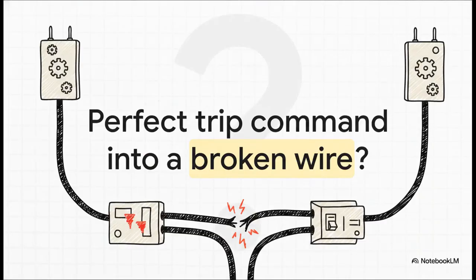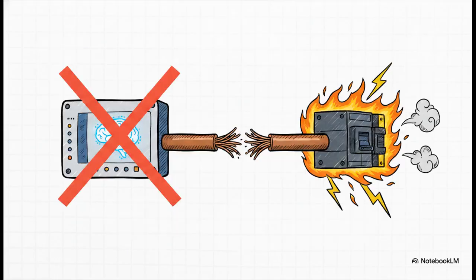Imagine this scenario for a second. Let's say every single protection function we've covered so far is working flawlessly. Your differential protection is spot on, your thermal and overcurrent elements are perfectly tuned, a fault happens, the relay instantly and correctly detects it, and it fires off that critical trip command to the breaker. But what actually happens if the physical wire connecting the relay to the breaker is severed? Nothing. Absolutely nothing. And honestly, that is a terrifying prospect.